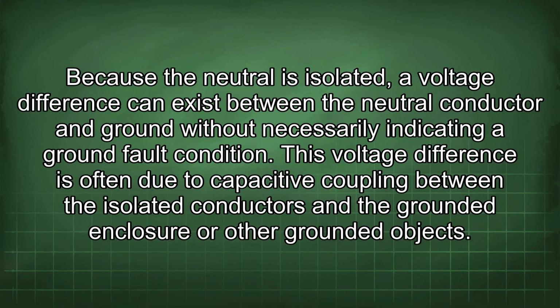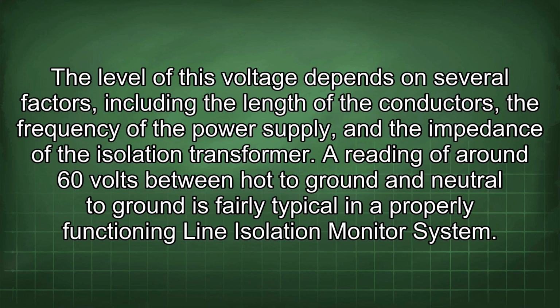Because the neutral is isolated, a voltage difference can exist between the neutral conductor and ground without necessarily indicating a ground fault condition. This voltage difference is often due to capacitive coupling between the isolated conductors and the grounded enclosure or other grounded objects. The level of this voltage depends on several factors, including the length of the conductors, the frequency of the power supply, and the impedance of the isolation transformer. A reading of around 60 volts between hot to ground and neutral to ground is fairly typical in a properly functioning line isolation monitor system.